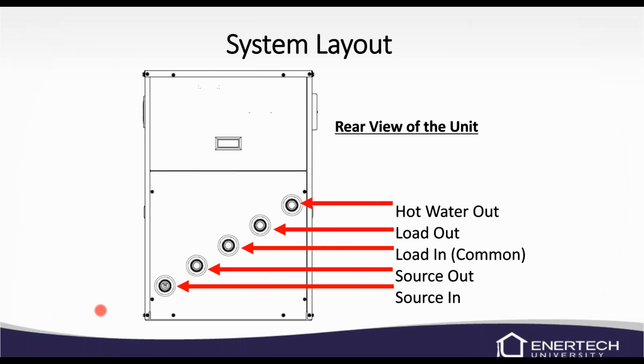This is the back of the unit. So the water lines come out the back of the unit, so we can't slide this up against the wall. We've got to have a little bit of clearance. Now, these are all double O-ring fittings, so you've got to use the double O-ring fitting. It's going to be double O-ring by hose barb because you're going to have rubber hoses coming off there.